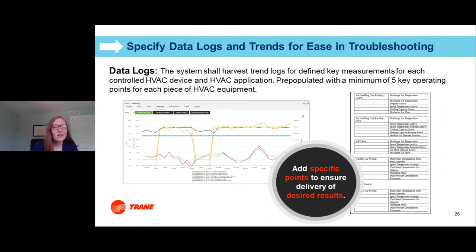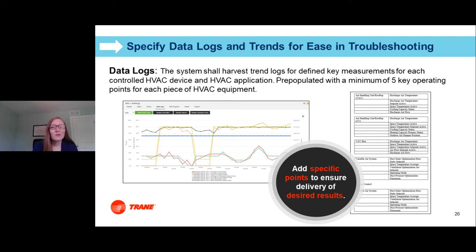Data logs and trending are really valuable troubleshooting tools. How many times have you needed to set up a trend after a problem has occurred, then waited to see if it happened again to catch it? Strong specification language here can ensure that critical points are trended from the time the equipment is installed in the building automation system. This is valuable not only for owners, but also for engineers — it allows you to verify system operation during the warranty period.